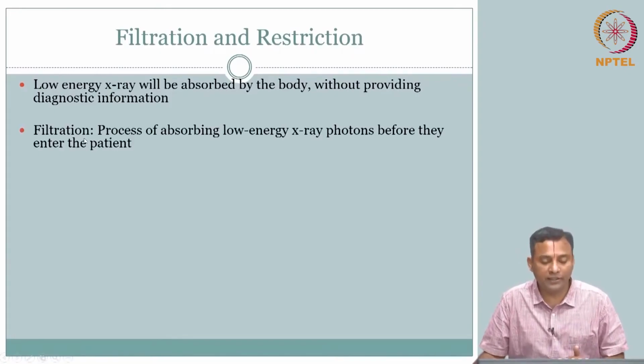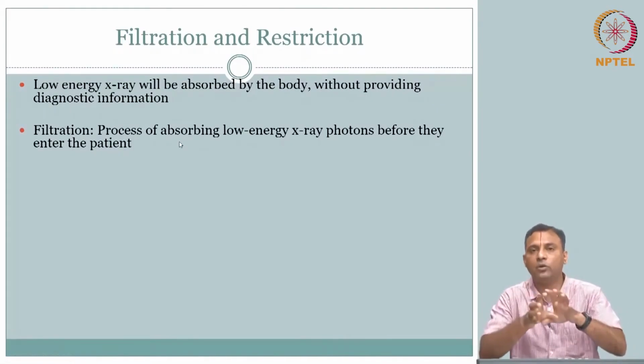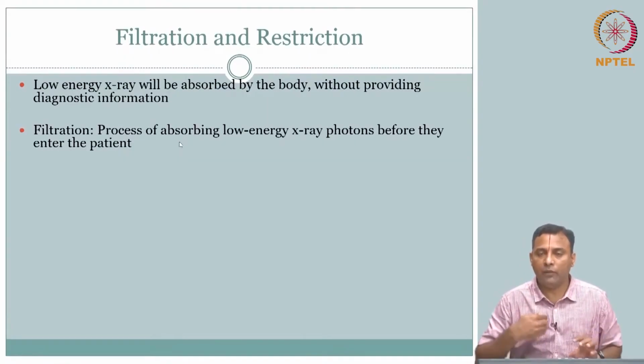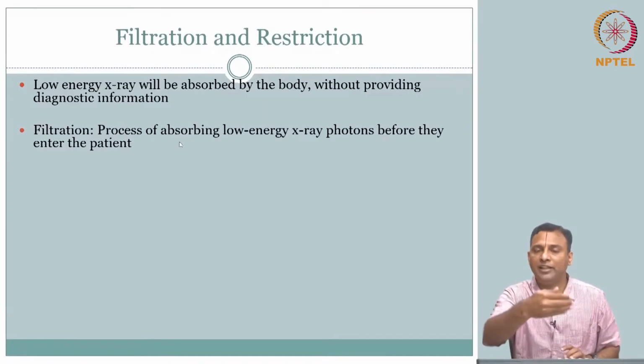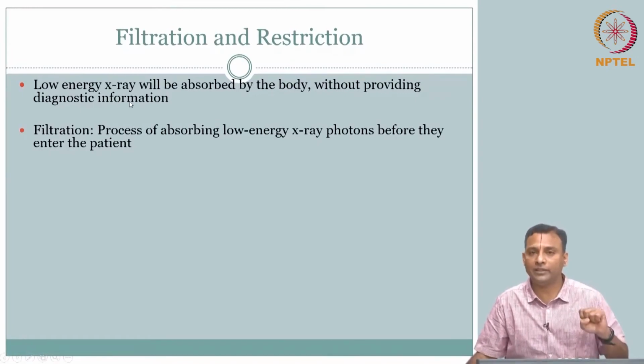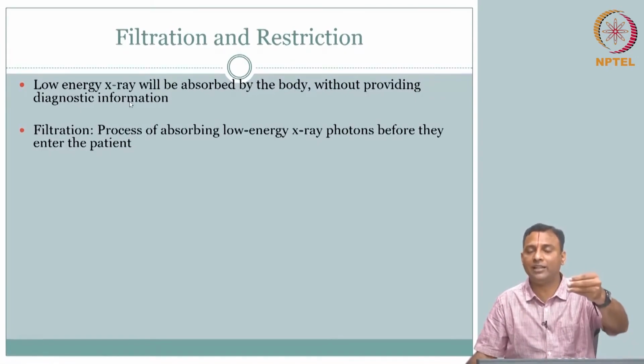So, what does filtration do? Filtration is the process of absorbing this low energy before it enters the patient. The X-ray tube is sending out X-rays, but before they can reach your body, I want to make sure I have some filters in place, so that I can take out all these low energy X-rays. It is better that the filter that we place absorbs the low energy.